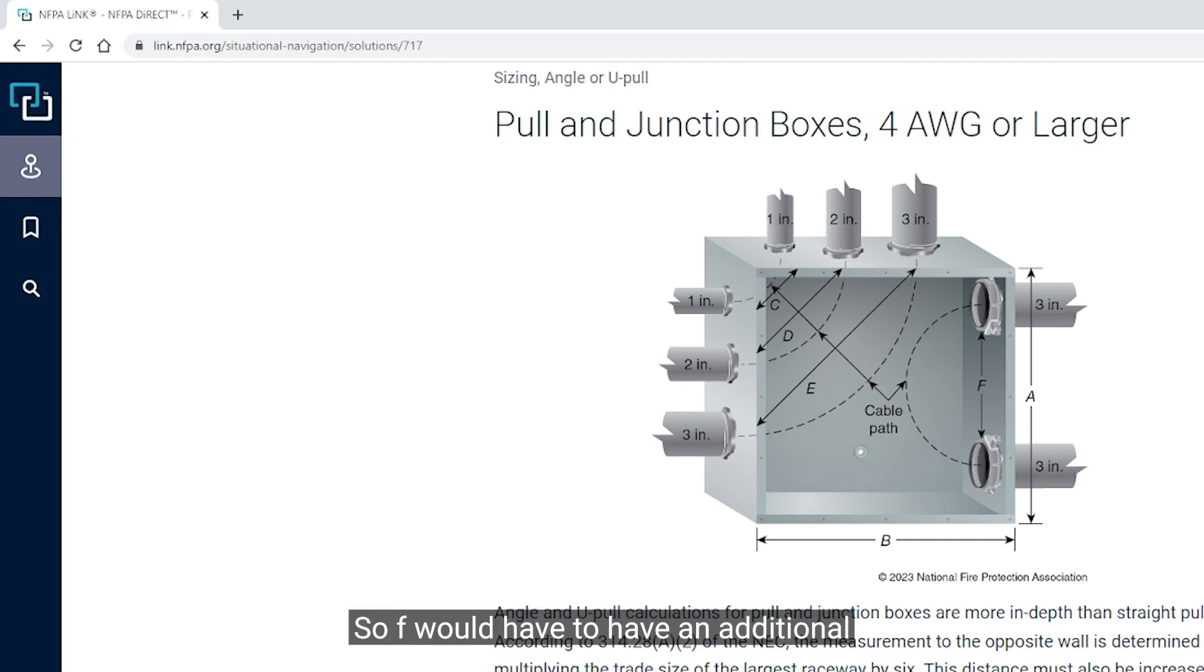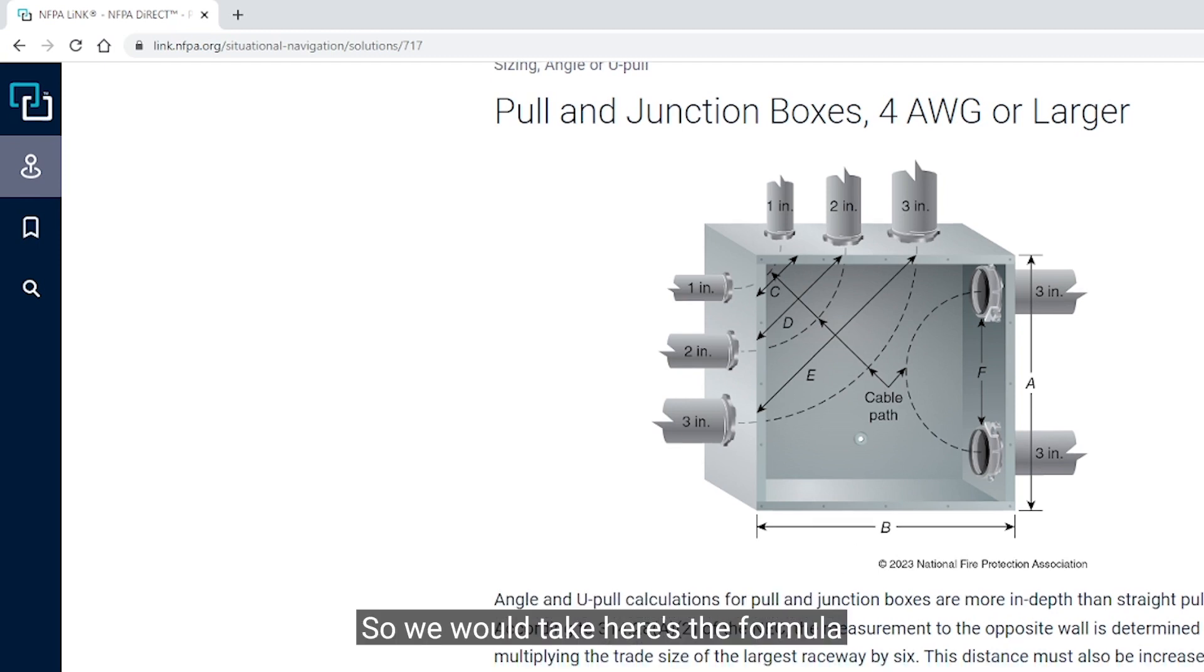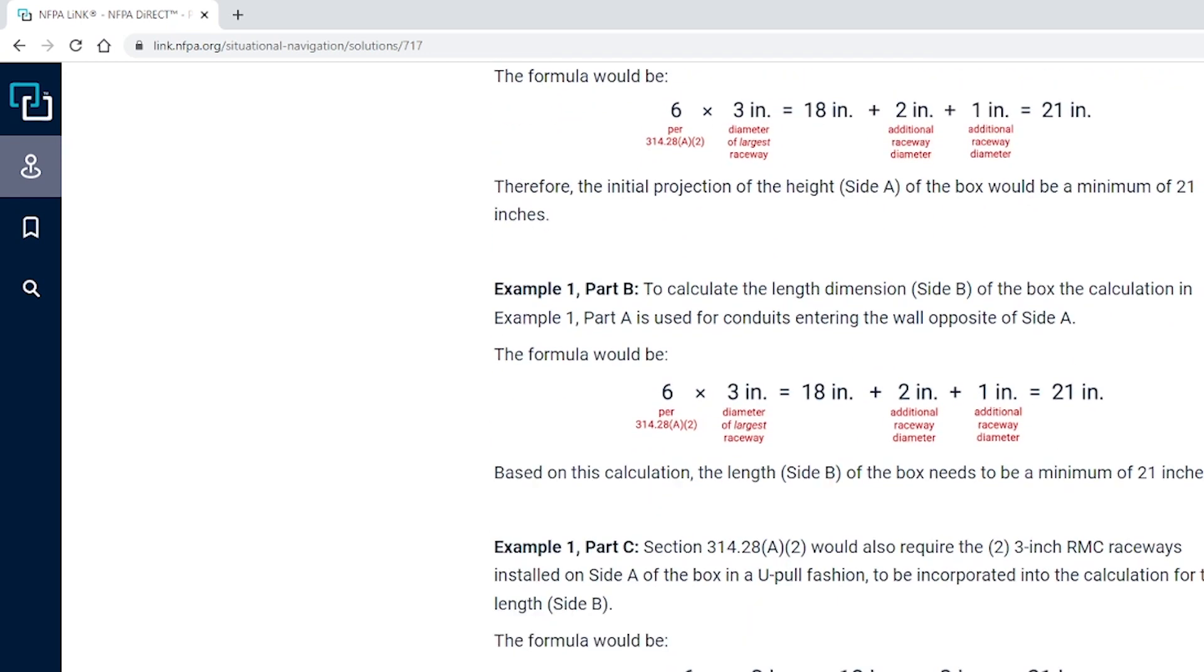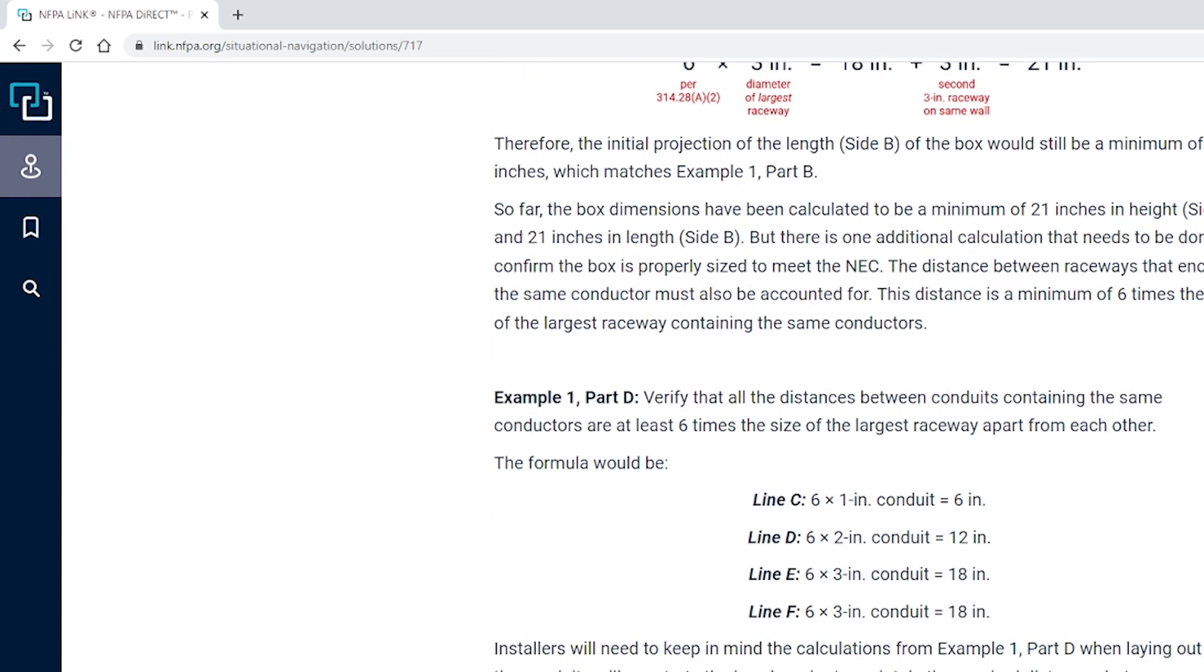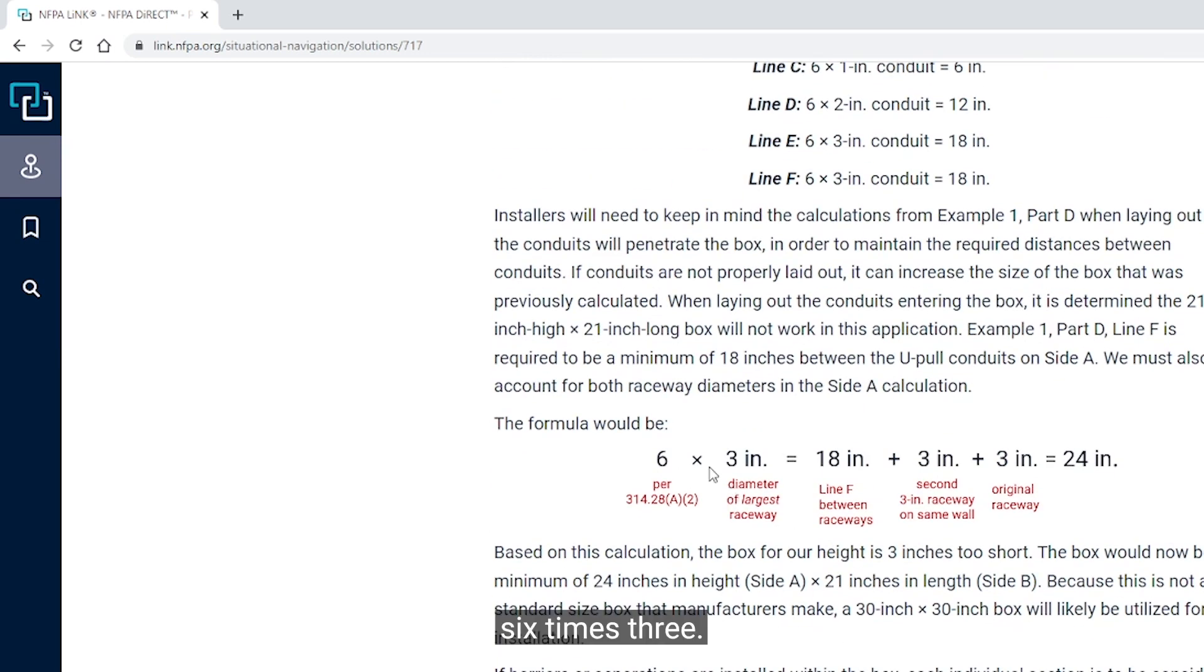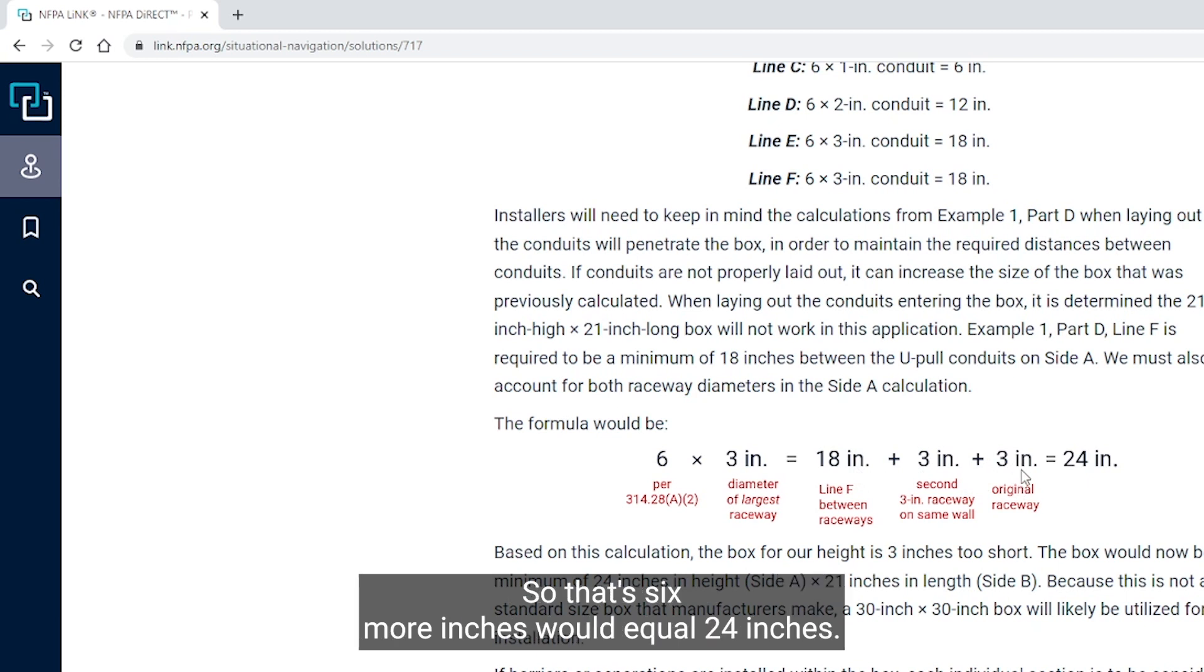So dimension side B, that lengthwise, 21 inches still probably would be okay. Line F, however, may cause us an issue. 6 times 3 equals 18, so this distance right here, line F, has to be 18 inches. Now in order to get that, we have to take into account the diameters of these raceways, top and bottom. So F would have to have an additional 6 inches added to it. The formula: 6 times 3, so that's the largest raceway, is 18 inches, so that's 18 inches between the raceways, plus 3 inch, plus 3 inch, so that's 6 more inches, would equal 24 inches.